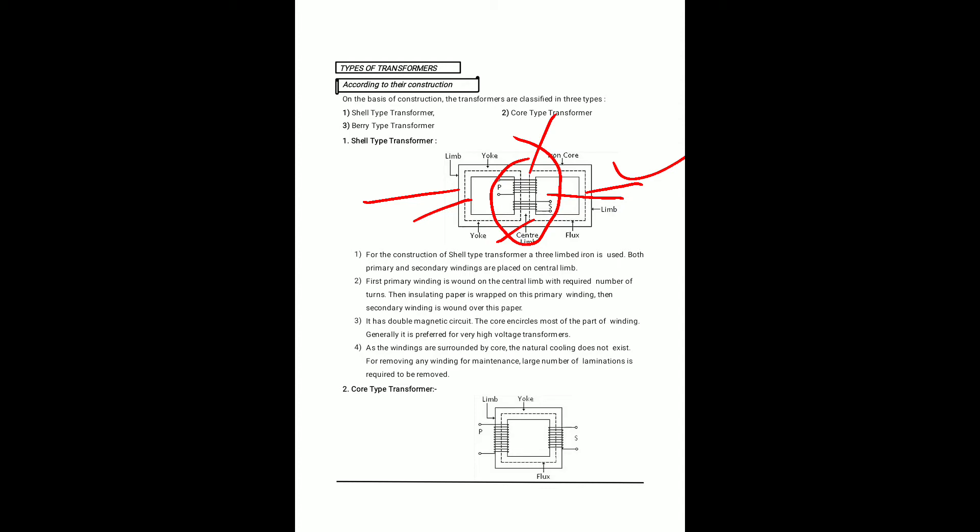In the shell type, the primary winding is wound on the central limb with the required number of turns, then insulating paper is wrapped and the secondary winding is wound over it. It has a double magnetic circuit. The core encircles most of the winding and is generally preferred for very high voltage transformers. Natural cooling does not exist easily and a sandwich type winding with a large number of laminations is required.